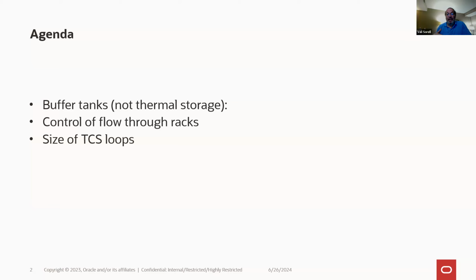For those who are following ASHRAE, the classification for water to the chip is called the S class. So S40 means no higher than 40 C to the chip. S35, no higher than 35 C to the chip. S30 just left ASHRAE two days ago. And at ASHRAE, the IT subcommittee discussed going to S20, S15, S10, only because the demand has increased so quickly that we need to get colder and colder water from a cooling plant, chiller plant, basically.